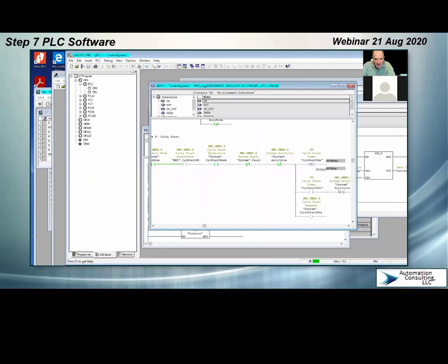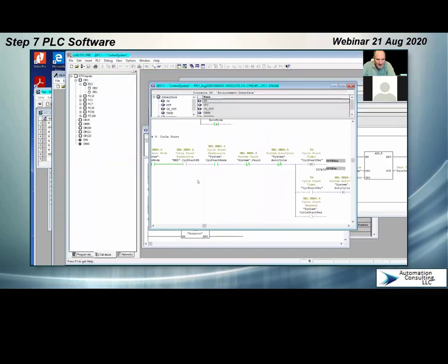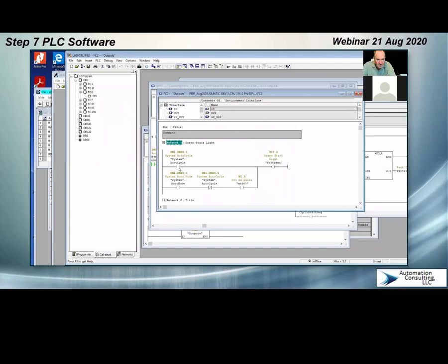The timer runs, I latch in auto cycle. What's actually making this blink is if I go here into the outputs routine, I have a little clock. And you can see if I'm in auto cycle, it doesn't blink. If I'm not in auto cycle, I use this little 500 millisecond pulse. This pulse comes from the hardware setup.